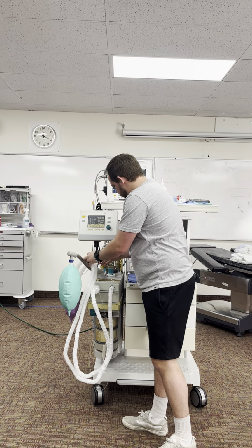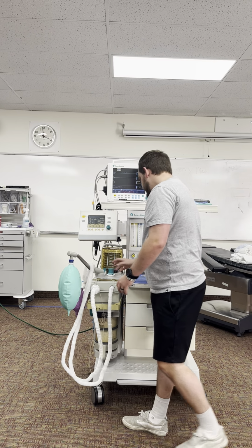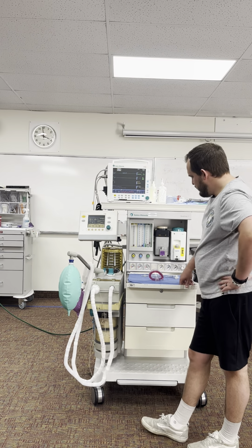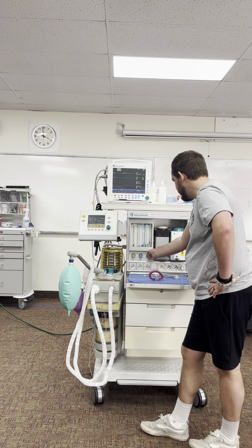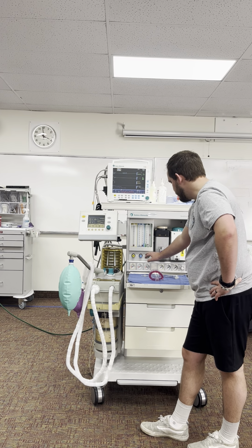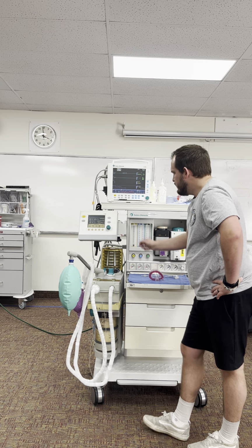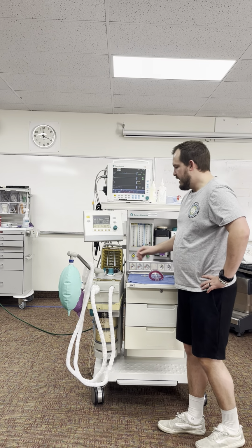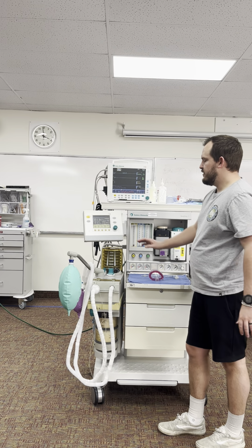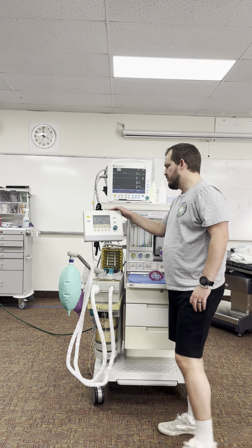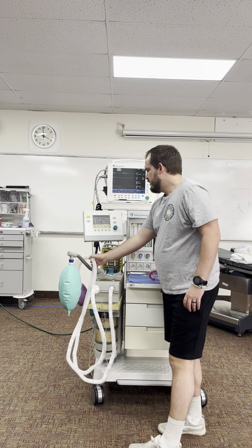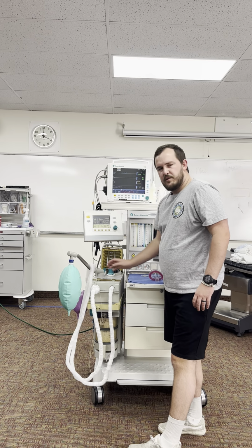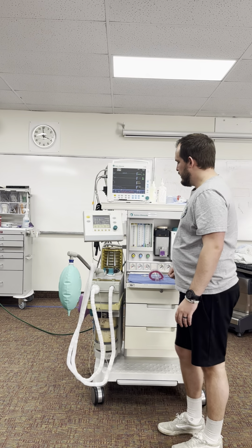I'm gonna switch over to my ventilator, and I'm going to assess my bellows and my ventilator. So the bellows needs to go all the way up to help it increase. I'm just gonna increase my flow. We're good there. And then I'm just evaluating, since we have the pediatric artificial lung on, my volumes are set lower, so my volumes are only set to 250. So anything above 200 is adequate, which is what we have.